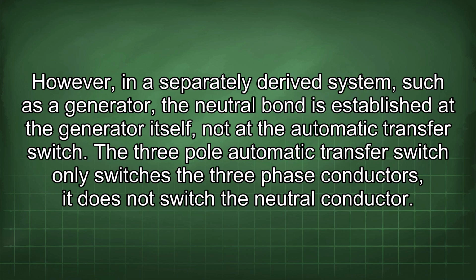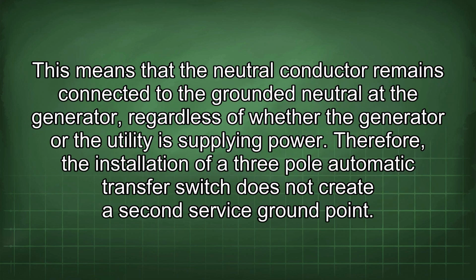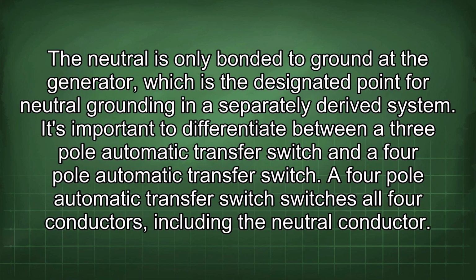The 3-pole automatic transfer switch only switches the 3-phase conductors. It does not switch the neutral conductor. This means that the neutral conductor remains connected to the grounded neutral at the generator, regardless of whether the generator or the utility is supplying power. Therefore, the installation of a 3-pole automatic transfer switch does not create a second service ground point. The neutral is only bonded to ground at the generator, which is the designated point for neutral grounding in a separately derived system.